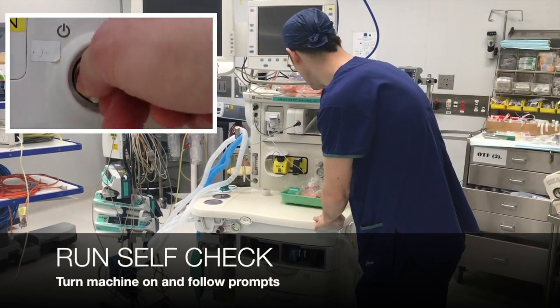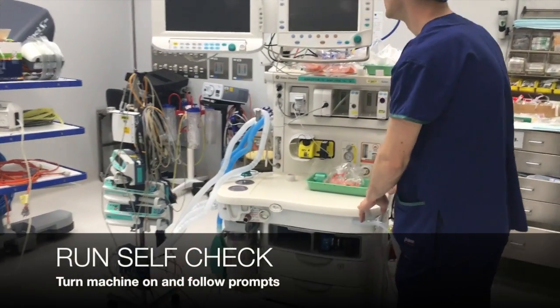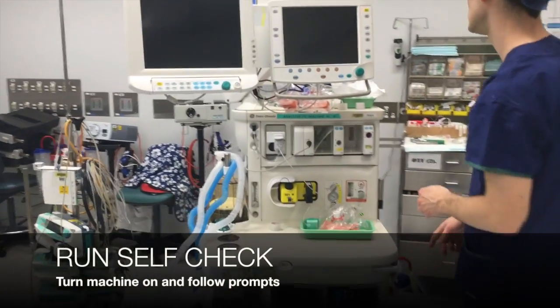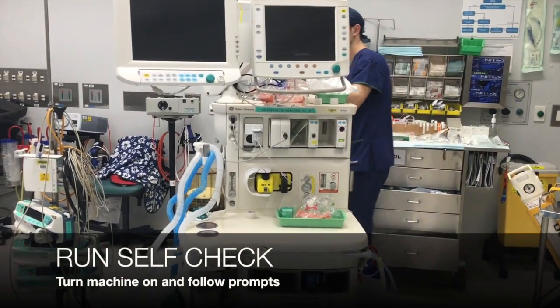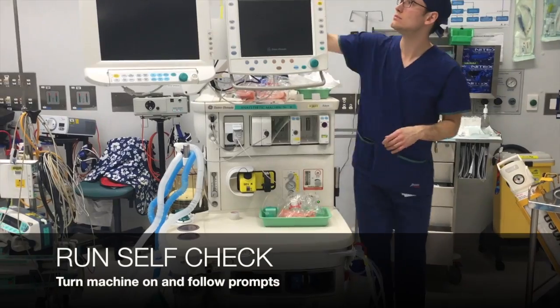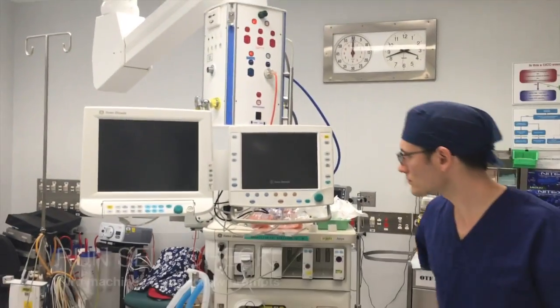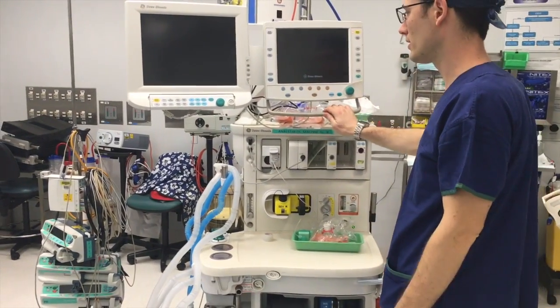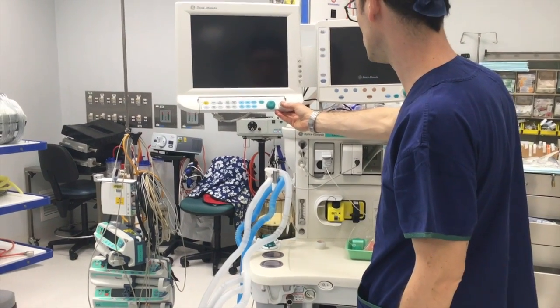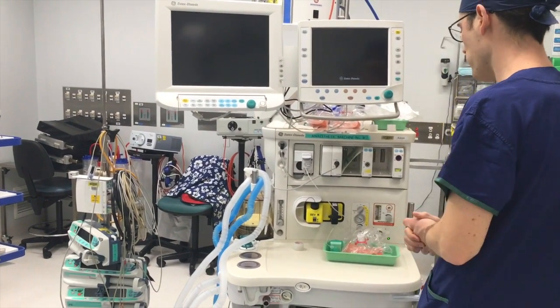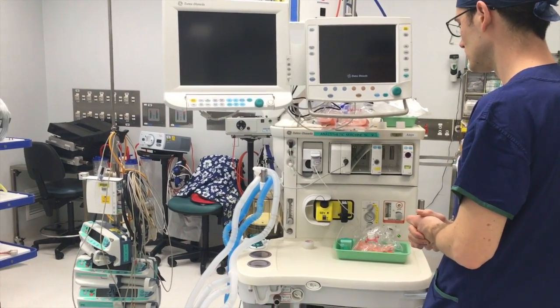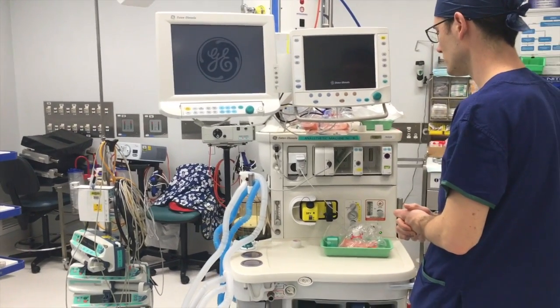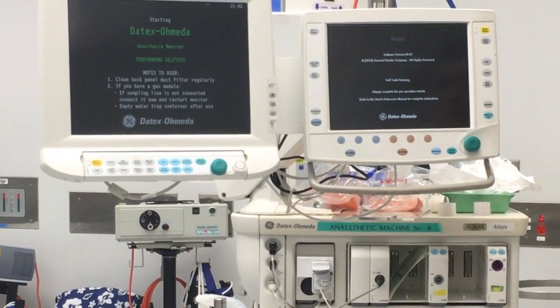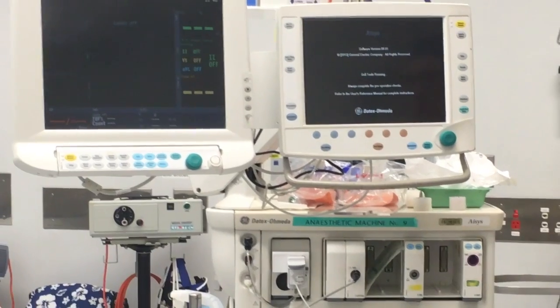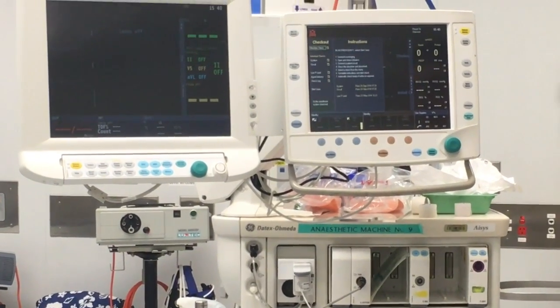First, turn the machine on to start running the self-check. While the machine boots up, it's a good idea to check that the power cable is plugged into the correct outlet. As the machine startup can take some time, it's also a good chance to turn on other monitoring and also think about other equipment and medications you might need. Once the monitors get to their home pages, it's time to start the specific checks.